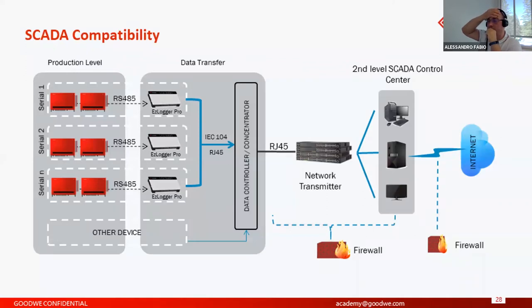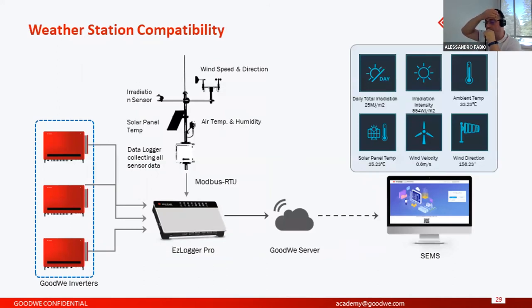Another, for example, for utility scale or big plants, we have SCADA compatibility. So also with our data logger, the EzLogger Pro, with the IEC-104 protocol through the RJ45 connection, we have the possibility to go to the SCADA interface, so an external SCADA interface, and then to the internet if you want, for big projects. Also for weather station compatibility, with our EzLogger Pro, this is our data logger, we can also connect, for example, a weather station with an RS-485 connection through Modbus RTU, and we can then send the data directly to the SEMS portal. We can provide also some topology that you can use, compatible with our communication protocol.